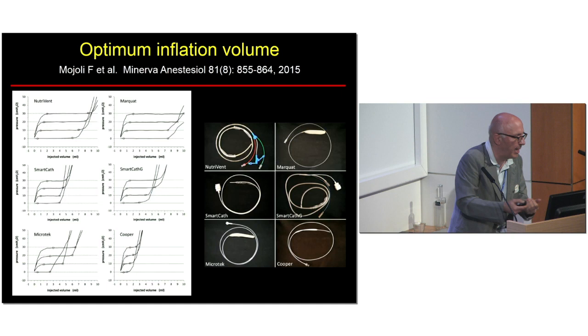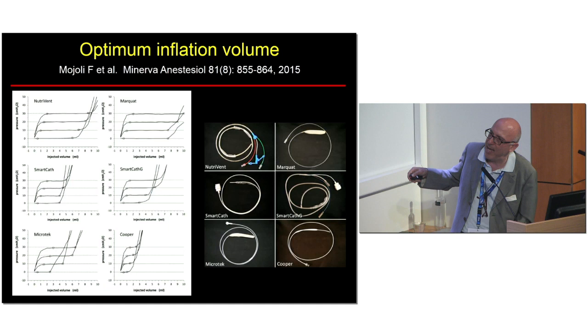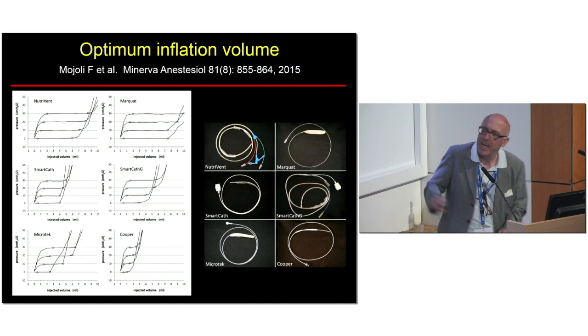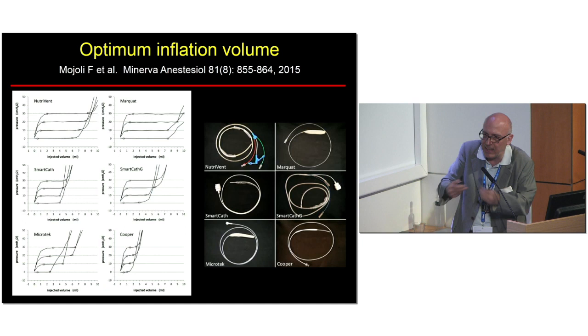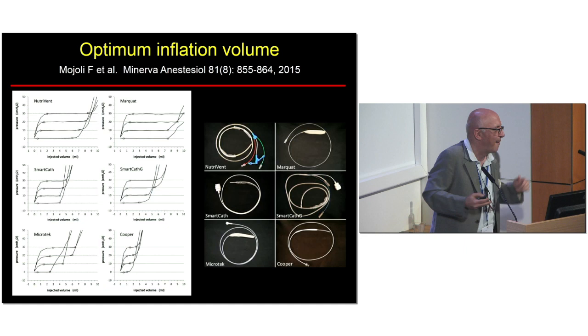First of all, you see that the amount of volume at which you have a flat curve—meaning the pressure does not change with the inflation volume of the balloon—changes dramatically from 1 to 2 milliliters for each catheter. So each catheter has a different compliance of the balloon, which is a problem, because you get completely different measurements.